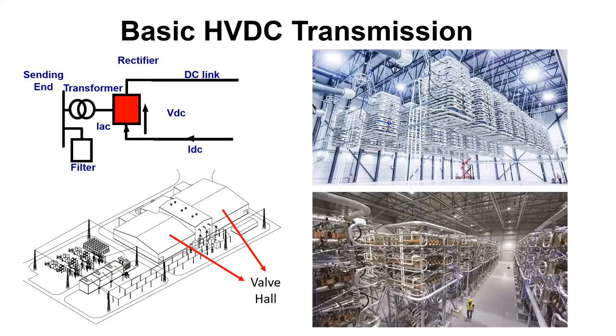For example, one of the primary pieces of equipment in the converter station is the valve. The top picture shows a suspended arrangement for the valve, whereas the bottom picture shows the floor mounted arrangement. There are advantages and disadvantages associated with both. With the suspended type arrangement, maintenance is said to be easier or simpler than the floor mounted type. But the floor mounted type is said to be cheaper than the suspended type. Once again, please bear in mind that a lot goes into the design of the HVDC system, which I'm not covering today.